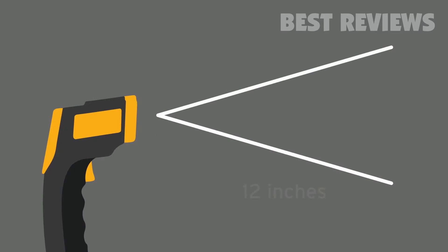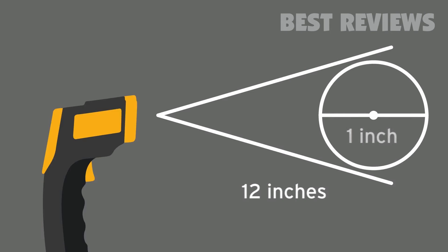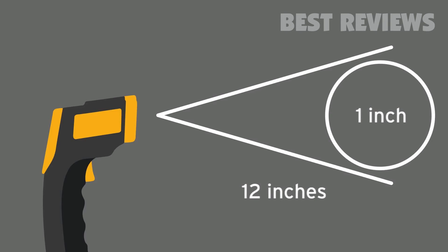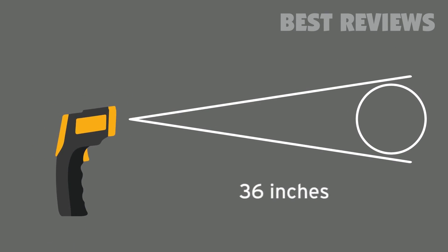Keep in mind that the 774 has a distance to spot ratio of about 12 to 1. That means for every 12 inches between the LaserGrip and the point of measurement, the measurement spot diameter increases 1 inch. If you're standing 12 inches away from the point of measurement, that's a 1 inch measurement spot diameter. At 36 inches away, that's a 3 inch measurement spot diameter.